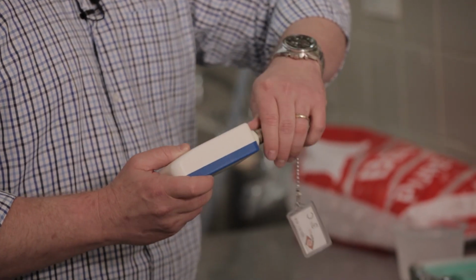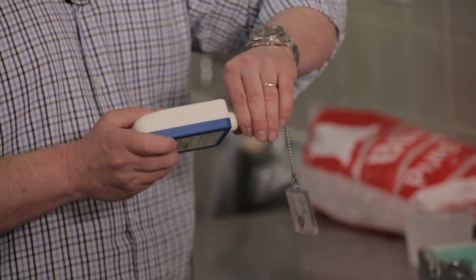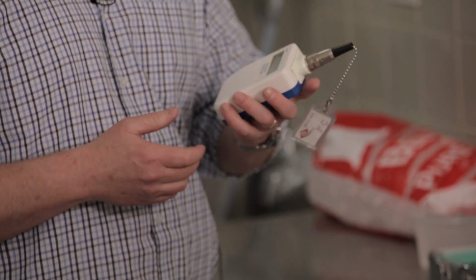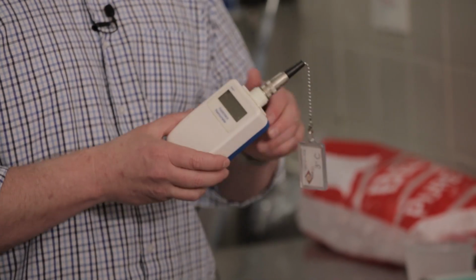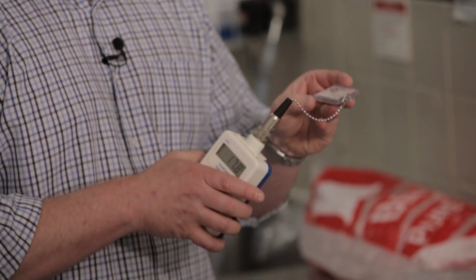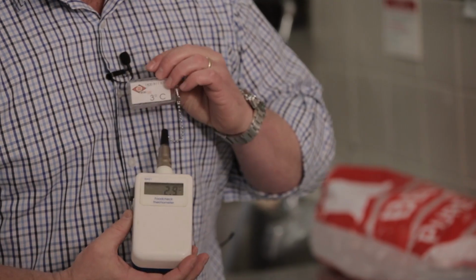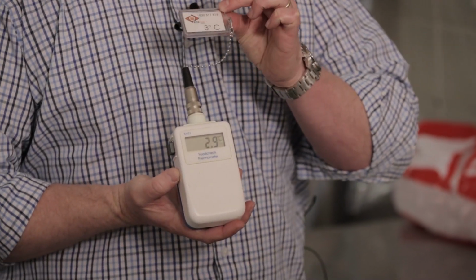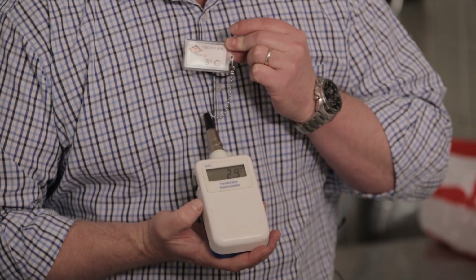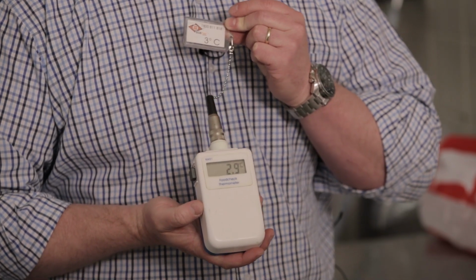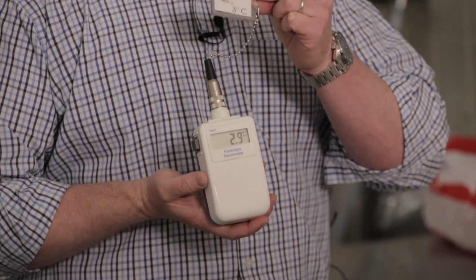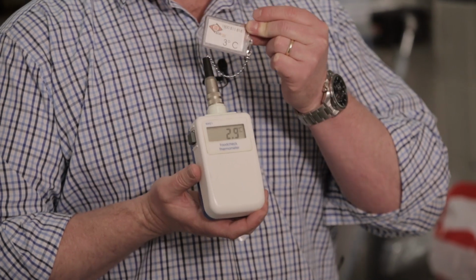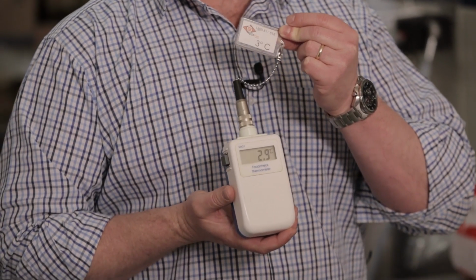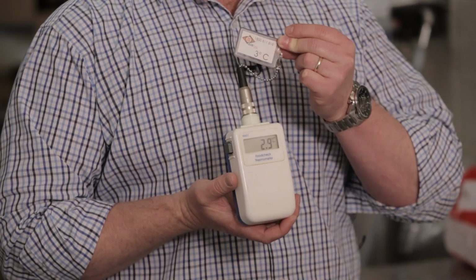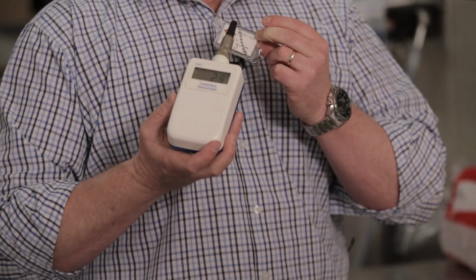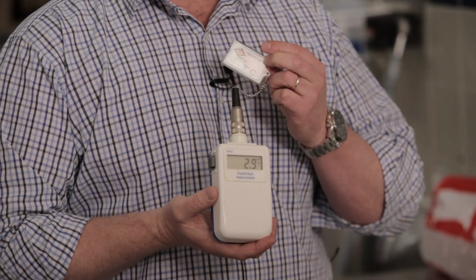to do it up. Now the reason why we do it up is to make sure that it's got a tight connection. If you don't have that tight connection, then it's probably not going to show you accurate details. So it's a 3 degree test piece. You turn on your digital thermometer, and as I said, it's electronically calibrated, these test pieces. That's telling me that this digital thermometer is at 2.9 degrees. Now, we don't need it to say 3 degrees. The accuracy for these test tags is about 0.3 or 0.4 degrees. So as long as it's between that, we're very happy that the digital thermometer is accurate.